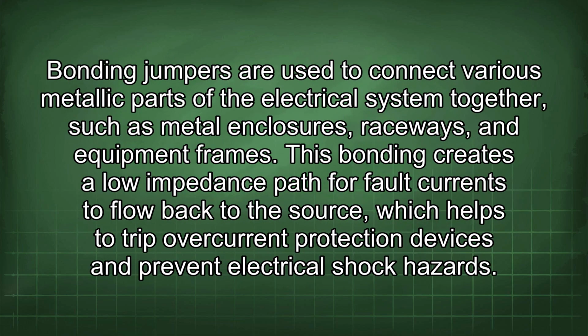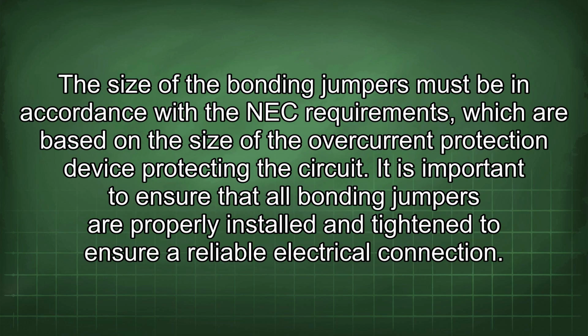Bonding jumpers are used to connect various metallic parts of the electrical system together, such as metal enclosures, raceways, and equipment frames. This bonding creates a low impedance path for fault currents to flow back to the source, which helps to trip overcurrent protection devices and prevent electrical shock hazards. The size of the bonding jumpers must be in accordance with the NEC requirements, which are based on the size of the overcurrent protection device protecting the circuit.